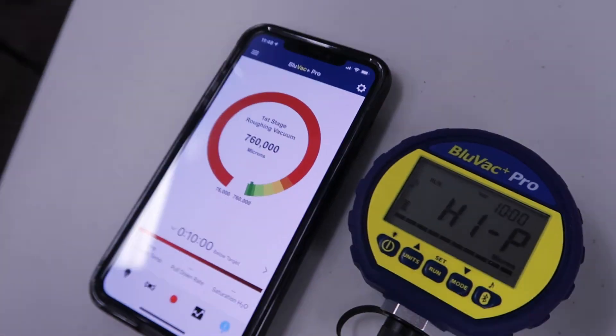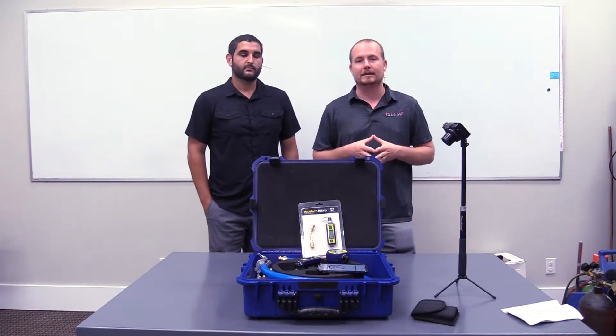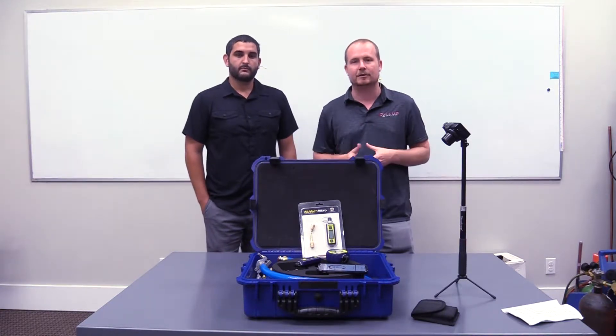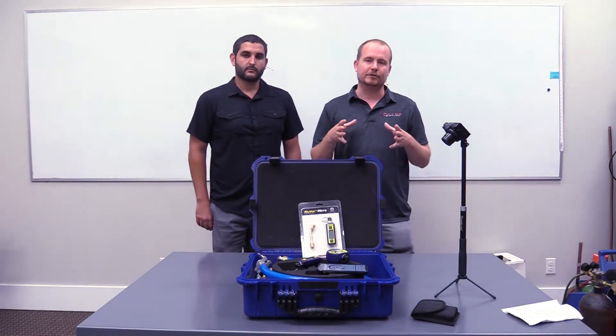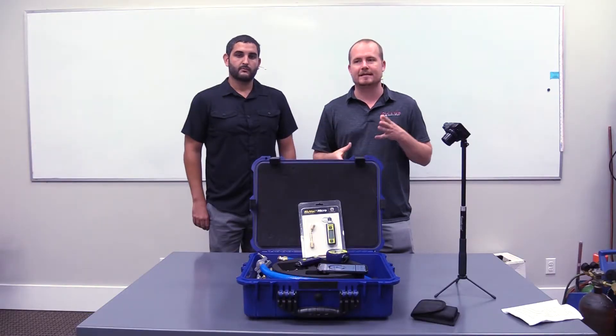My general recommendation is: if you really want to give a technician a gauge and have them use it without having to think too much — give them full instructions and they can essentially walk away and it does the work for them — then the Pro is the best option because you can preset those set points and it gives you instructions of exactly what to do. The BluVac Micro still gives you great graphing so you can see trends, but it doesn't give you the ability to put in those presets.